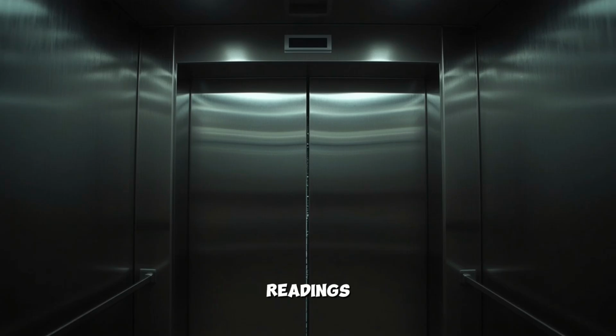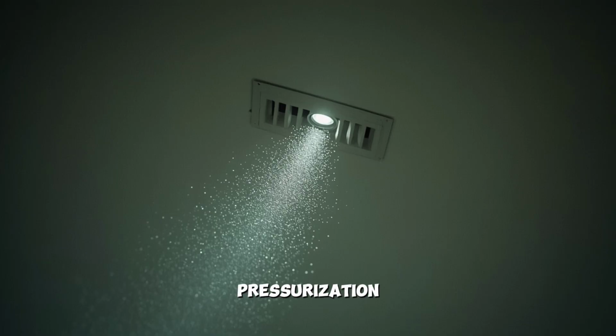Portable manometer readings taken at multiple lobby locations confirmed static pressures ranging from 0.22 to 0.31 inches of water column, well above the design targets and approaching the levels typically associated with temporary pressurization during fire alarm conditions when smoke evacuation systems activate. The engineers initiated manual adjustments to the building management system, reducing supply air volumes and opening return air dampers to relieve the pressure buildup.